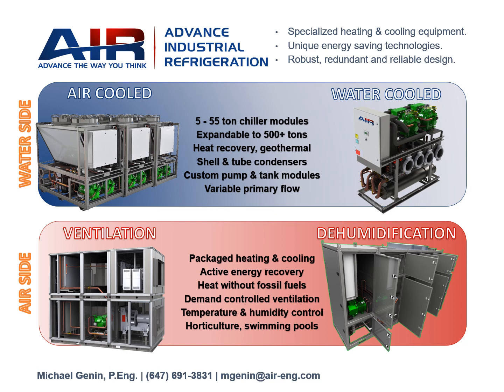Besides the compressor, is there any supplemental heat source that's required? Not really, unless you want to achieve a really warm supply air temperature. These things can be sized to deliver whatever kind of condition you need on the supply within reason. It's going to depend mostly on your exhaust air conditions.